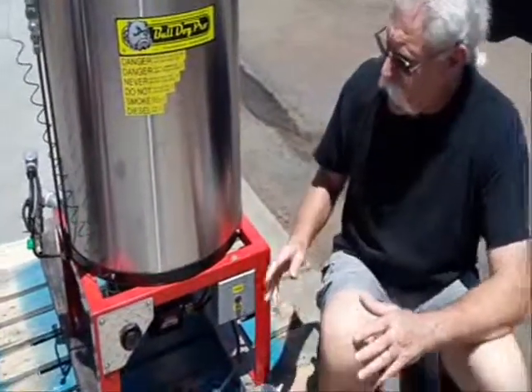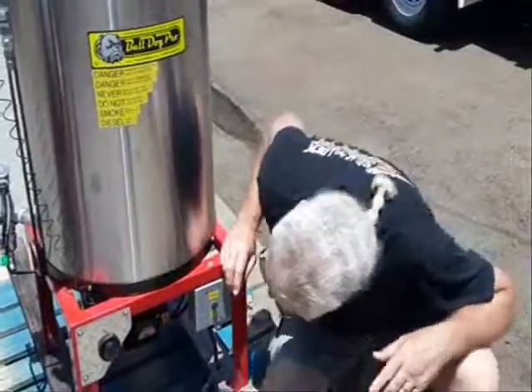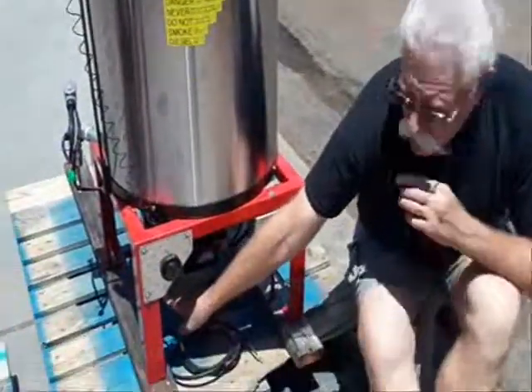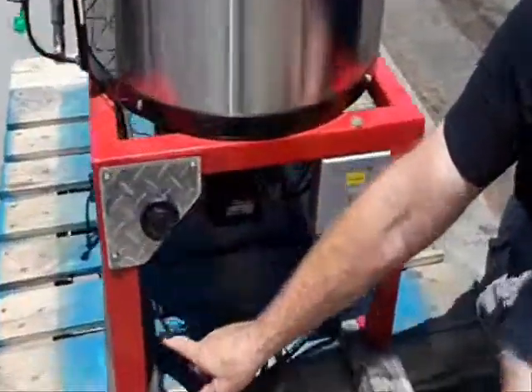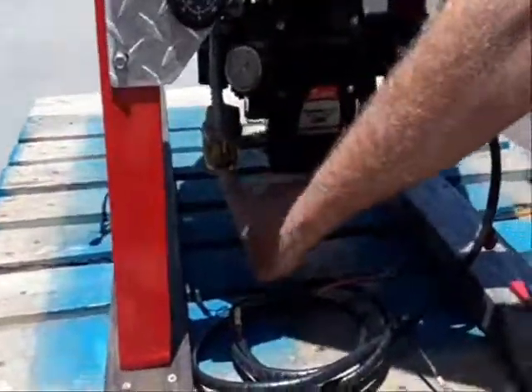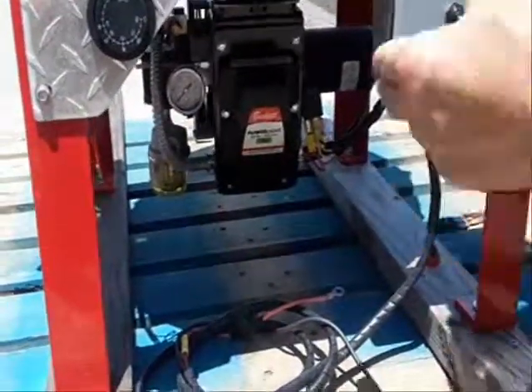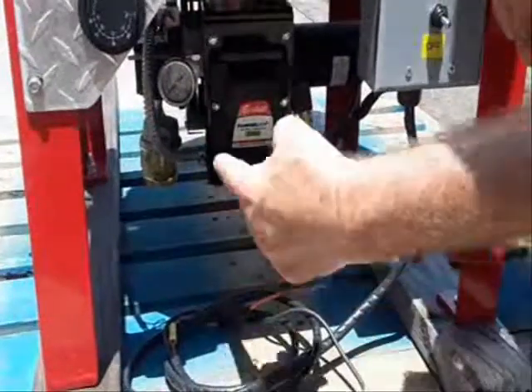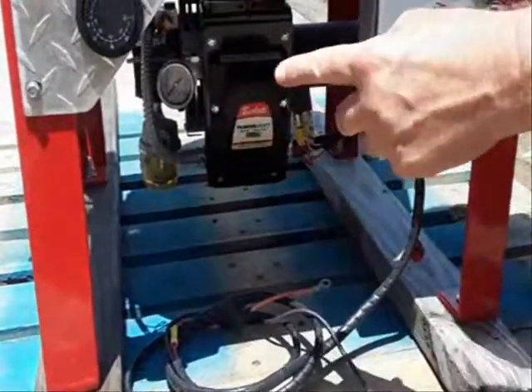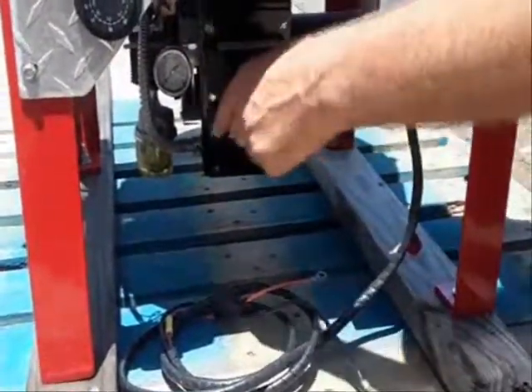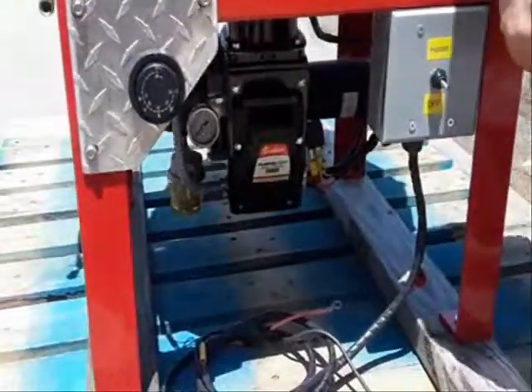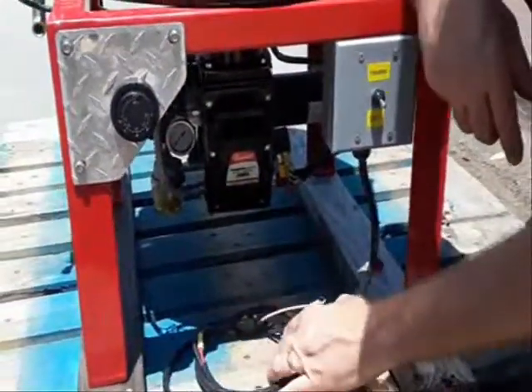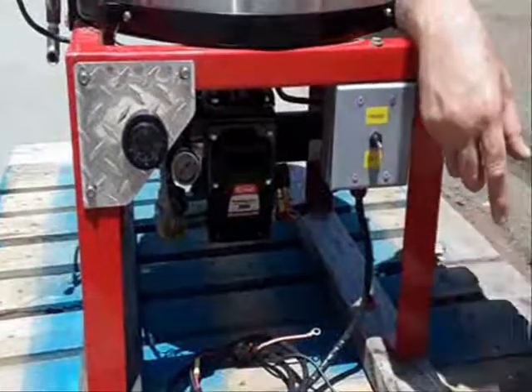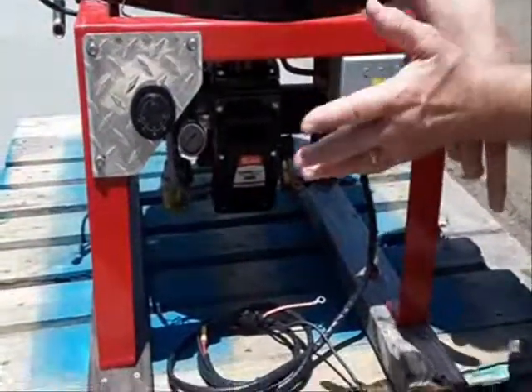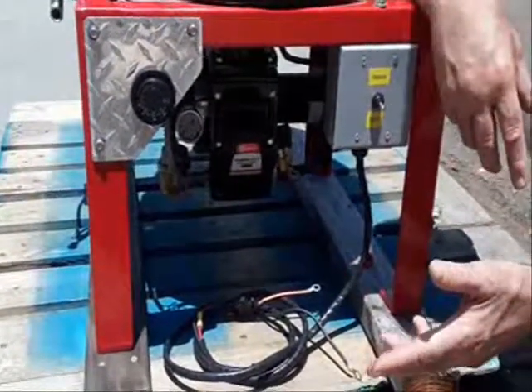Okay, the heater is going to have some fuel lines coming from the fuel pump. The one that goes to the filter right here is going to be your suction side line. It's going to suck the fuel in through the filter, and what fuel it does not use will be returned to the tank through the return line. Okay, so pretty simple. It can draw fuel uphill, not a big deal, from a pretty good distance.